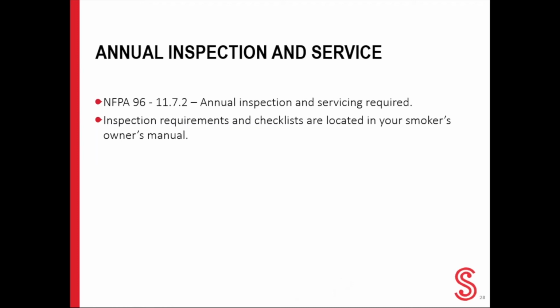In addition to the daily and weekly, there are some annual inspections and service also required. NFPA 96, Chapter 11.7.2 states that inspection and servicing of the cooking equipment must be made at least annually by a properly trained and qualified contractor. Inspection requirements and checklists are often found in your solid fuel appliance's owner's manual.